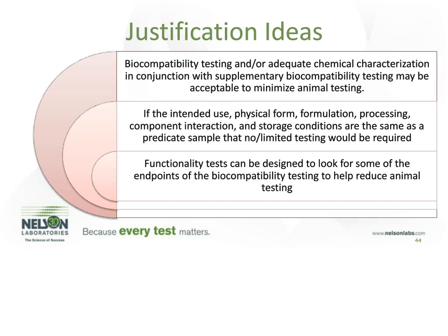So these are some of the endpoints you have to address in your overall assessment before you look at addressing it through testing. This next one is the one that I wish more people used, which is functionality testing to replace some of the biocompatibility. This is specifically with hemocompatibility, but all other endpoints can be used also. Lots of times these devices are put in functionality tests to make sure that they're working, and they use animals that are in clinically relevant conditions, in clinically relevant positions in the body. They might have weight on them if they're weight bearing, and so these are good predictors for biocompatibility, and we can use the evidence if the test is designed correctly, which you should work out with your testing lab. Even if you're not doing your functionality test in a CRO, most CROs should be able to help you set up a testing protocol to be able to address some of these biocompatibility issues. And these things can help you get out of biocompatibility testing.